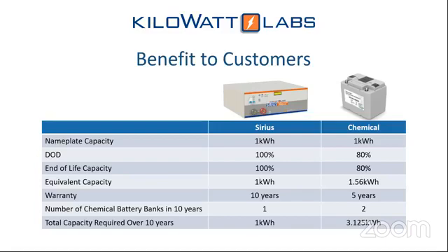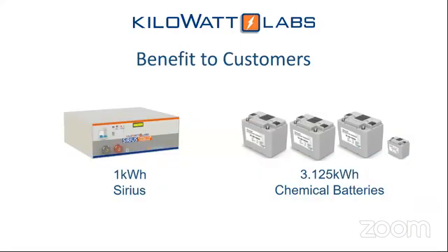So over 10 years, to get an equivalent of 1 kilowatt hour every day, every cycle, with Sirius you need 1 kilowatt hour. But with a chemical battery, you need to buy 3.125 kilowatt hours compared to the 1 kilowatt hour. This is a huge fundamental difference between supercap storage and chemical storage. I reiterate: the output given by 1 kilowatt hour of Sirius equals 3.125 kilowatt hours of chemical batteries. Sometimes it'll be less, sometimes more, but this is an average figure.